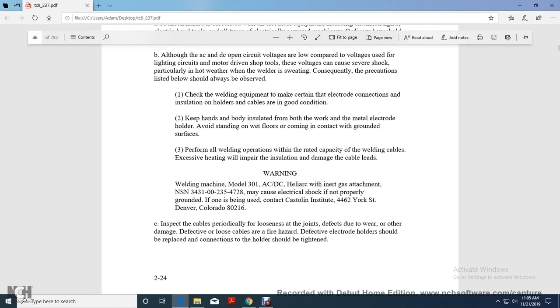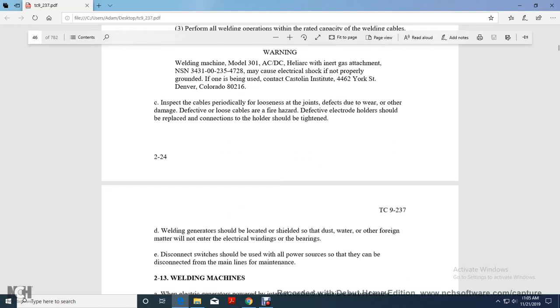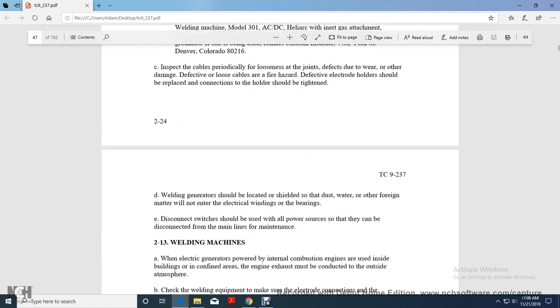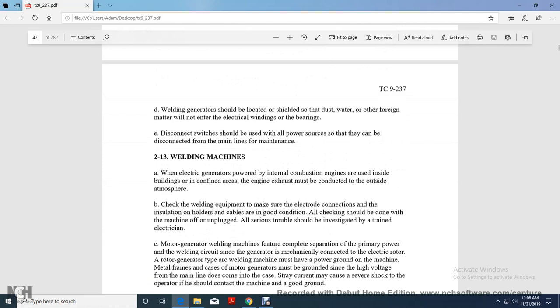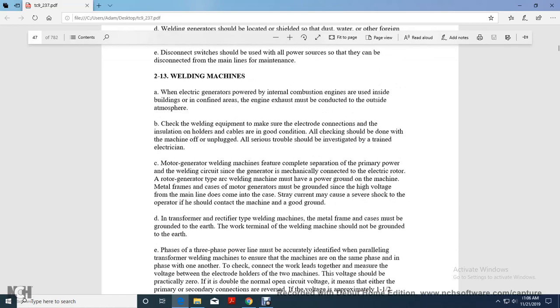Inspect cables periodically for loosened joints. Defects due to wear or other damage, defective or loose cables are fire hazards. Defective electrical holders should be replaced, and connections and holders should be tightened. Welding generators should be located with a shield so that dust, water, and other foreign matter will not enter the electrical winding and bearings. Disconnecting switches should be used at all power sources so they can be disconnected from the main line for maintenance.